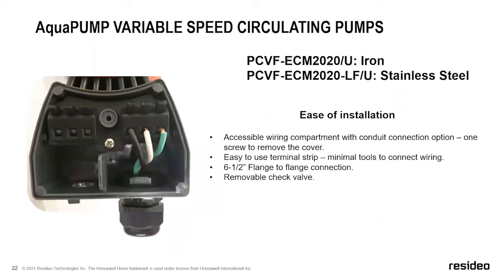And then I also get another question, well, how easy is it to wire up? At the end of the day, it's still kind of a tight package. I mean, if we were going to build this thing out with a giant box on it, it would look hideous, but we do have a little bit more room than some of our competition. So it's not too bad to hook up your high voltage side of this. And then if we look on the left-hand side, you'll see a couple other terminals that aren't hooked up. That is for your 0 to 10 or 4 to 20 milliamp connection. So I just wanted to give a visual indicator as far as the hookups.